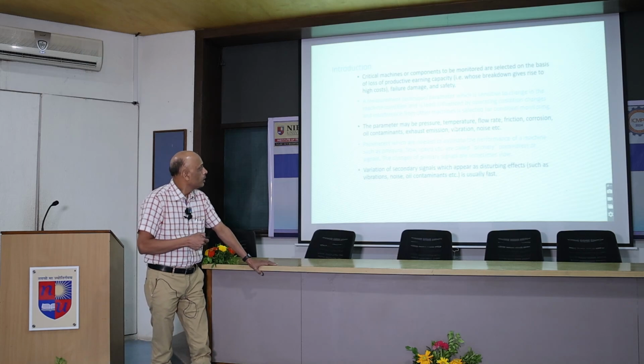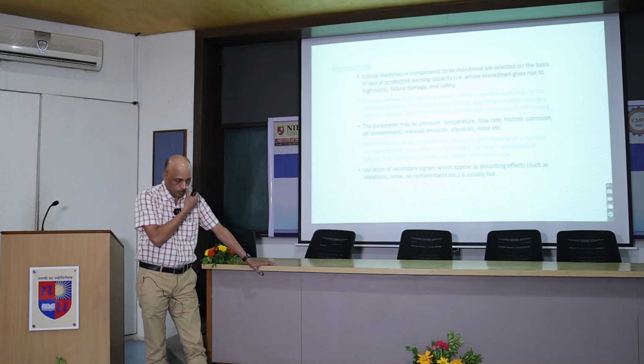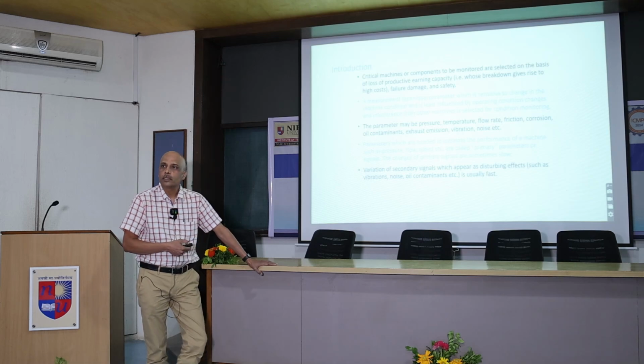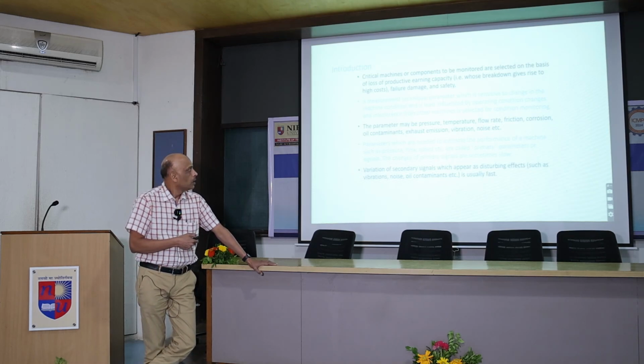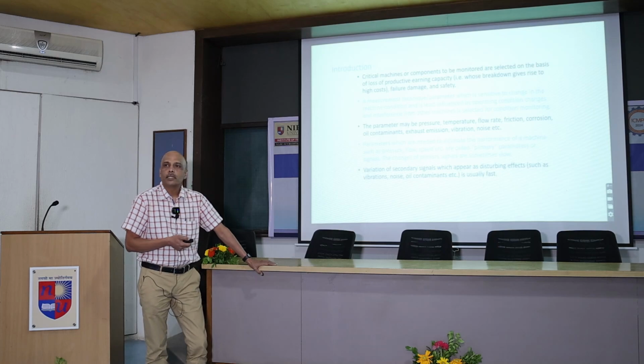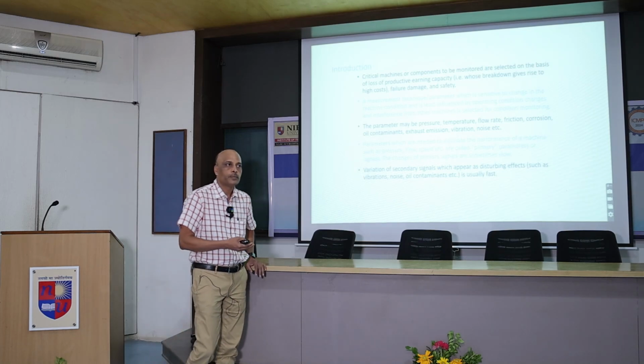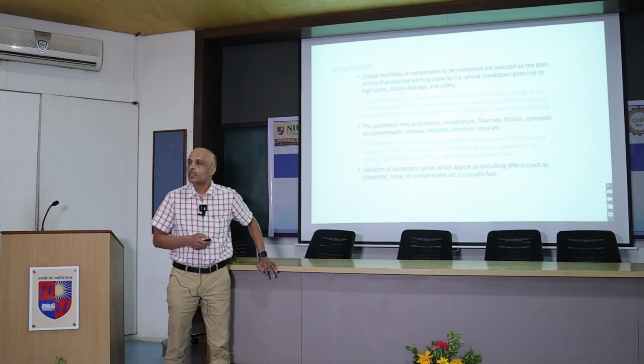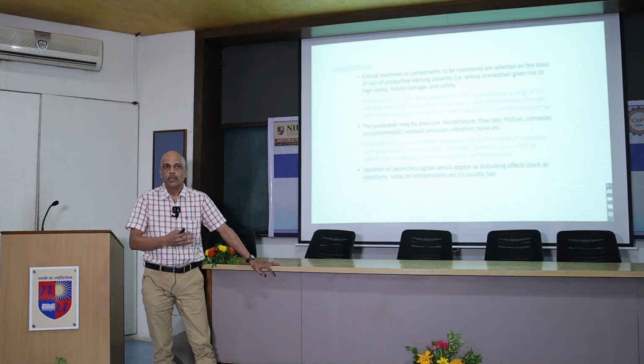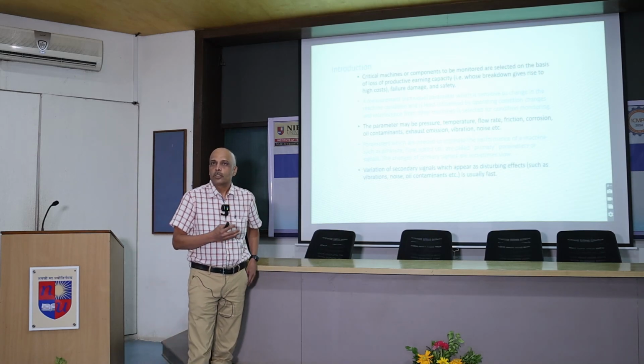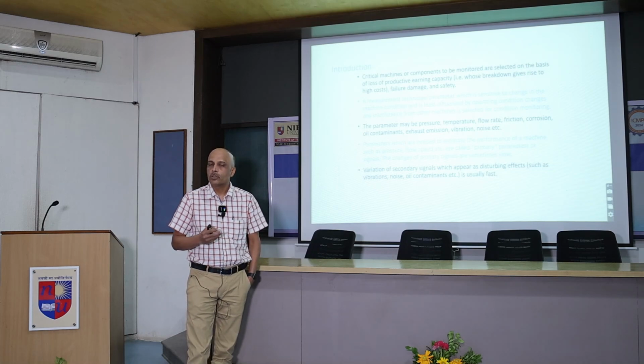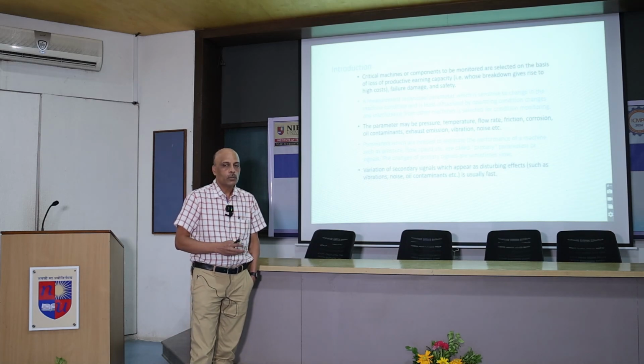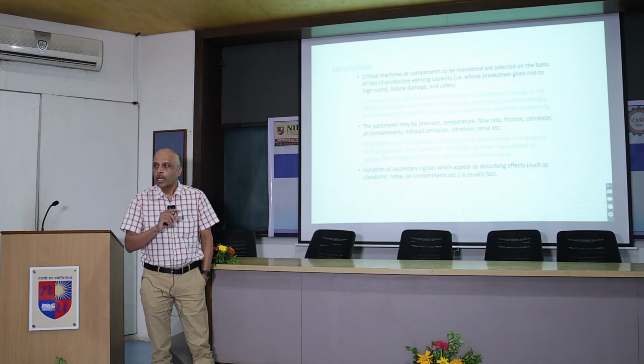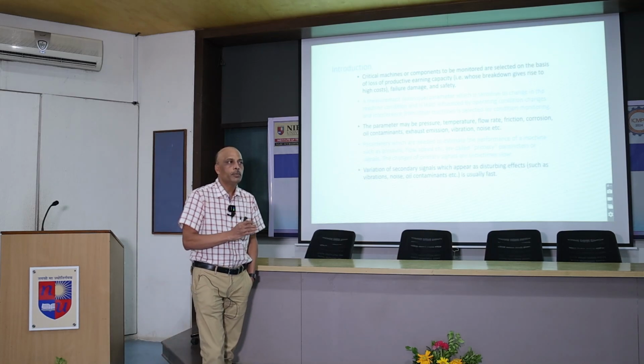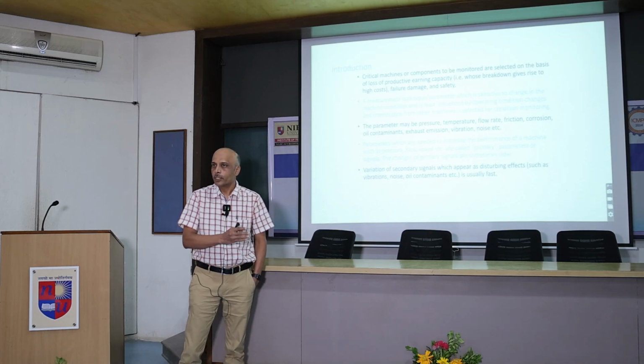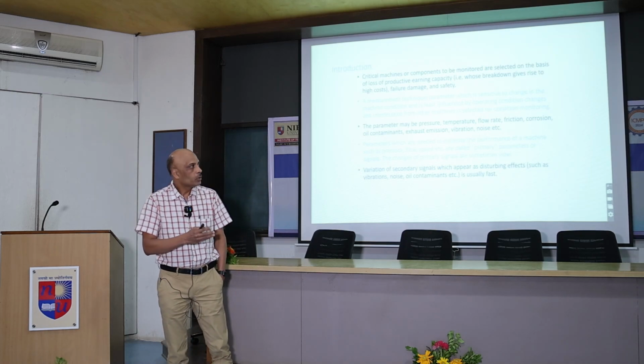Pressure and temperature are also some of these parameters, known as primary parameters, while others are called secondary parameters. Primary parameters are basically a function of the machine. For example, if you have a compressor, its main function is to increase pressure. So if you measure the pressure and see the required pressure has not been achieved, it means there is some malfunction in the compressor.